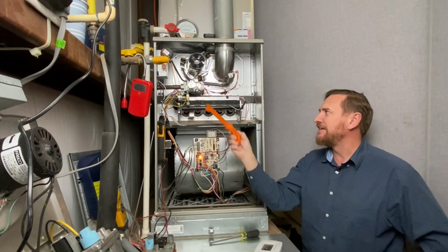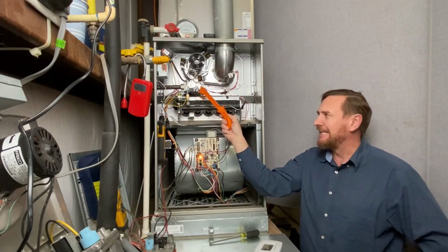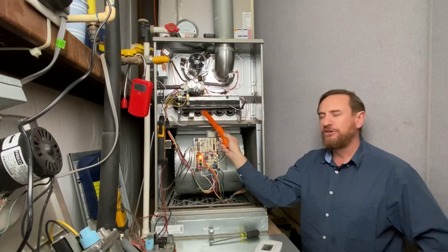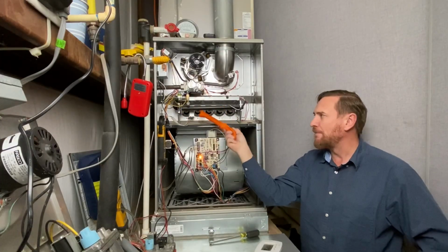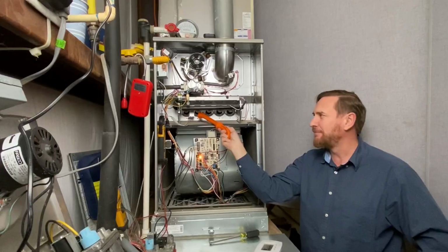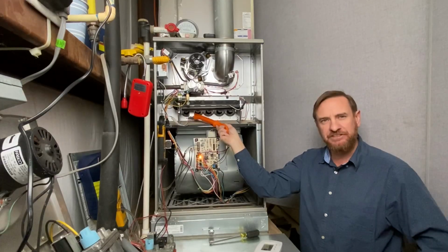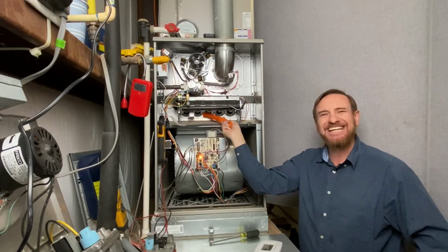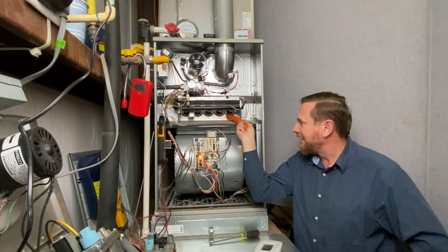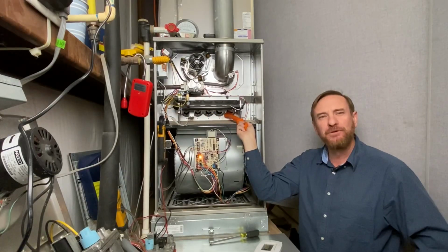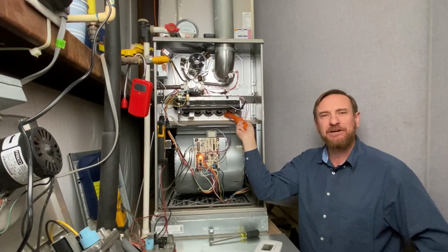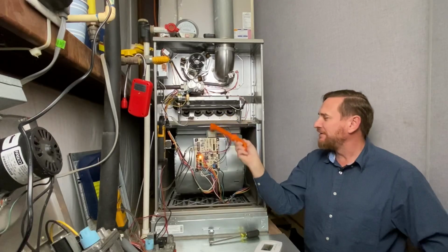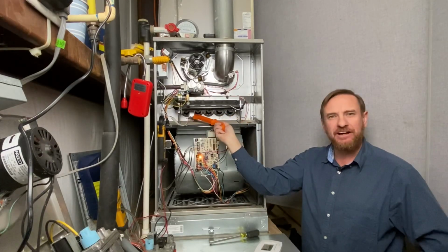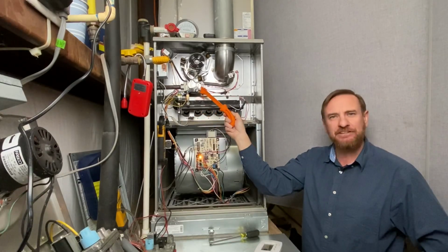The IFC then energizes the combination gas valve, allowing gas to flow through the manifold, to the spud, through the orifice, where it mixes with primary air inside the burners, across the hot surface igniter, where it ignites to a flame burning inside the heat exchanger. The flame sensor has a few seconds to prove a flame through a process called flame rectification. Once the flame is proven, the IFC shuts off the hot surface igniter and keeps the combination gas valve on.